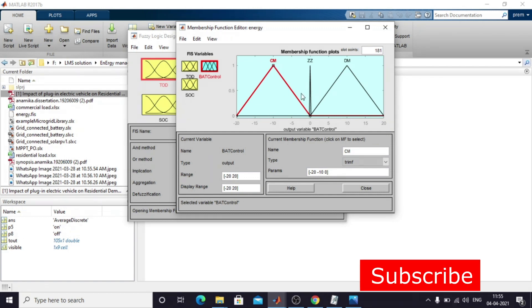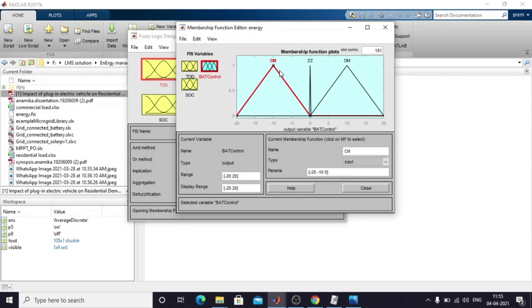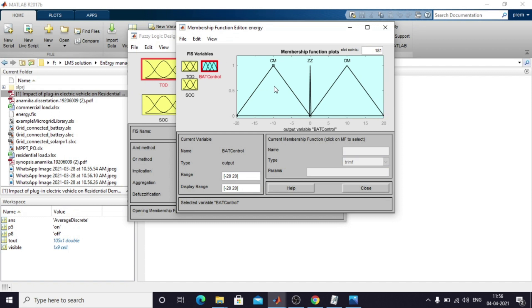Charging mode means the battery power should be in the negative direction — you need to feed a negative power reference to the battery. Discharging mode means you need to provide a positive power command to the battery to supply power to the load. In charging mode, you will receive power from the grid.